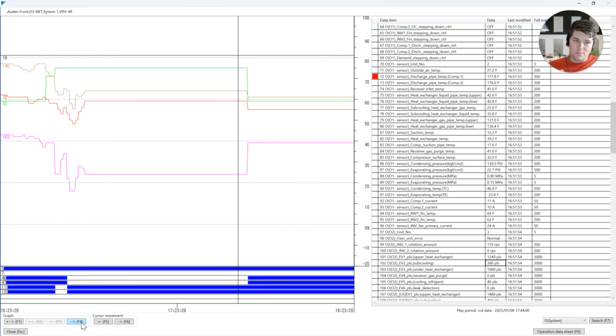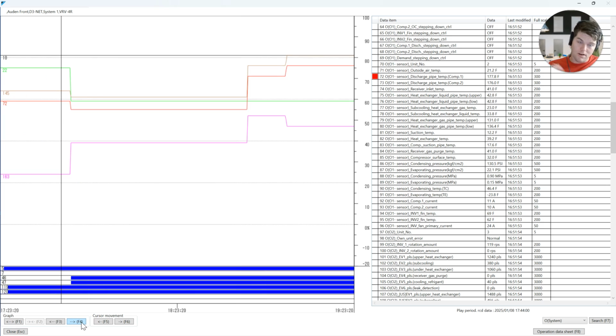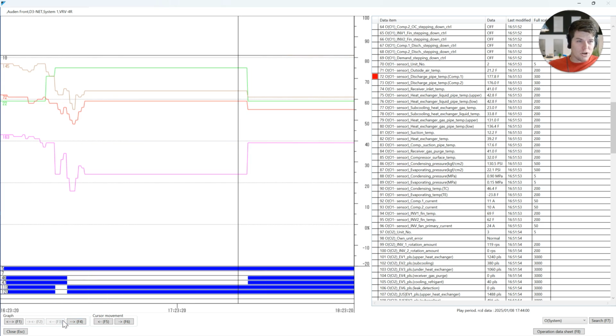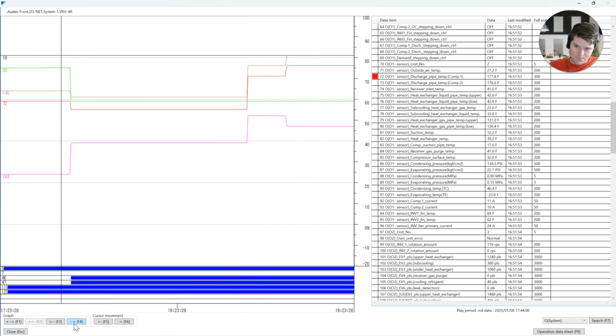I'm not a huge fan of troubleshooting in defrost. However, for the sake of duration of defrost and also quality of defrost at the time of switching, which we know is both poor. The other module, great. The second module, not so great. And you would say, well, Roman, would I be concerned about that module over the other? And I'd say, it depends. We've got to look at how the system operates over time to get a good feel of what we're looking at here. And you're going to see why I'm not worried about it over time.